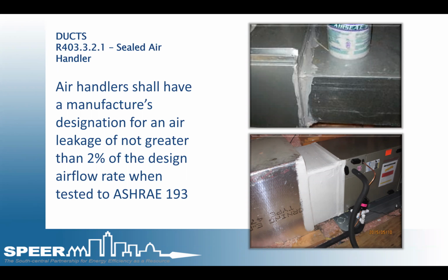Even 46 can be difficult at times, but it can and has happened. But for this to be consistent, that's asking a lot from the contractor. So sealing the cabinet and not having undue leakage, like the picture you see at the bottom, it basically shows a picture of a heat pump being very well sealed at the transition between the air handler and the supply plenum, but the contractor failed to mastic around the line set pipes, the condensation piping coming from the cabinet.